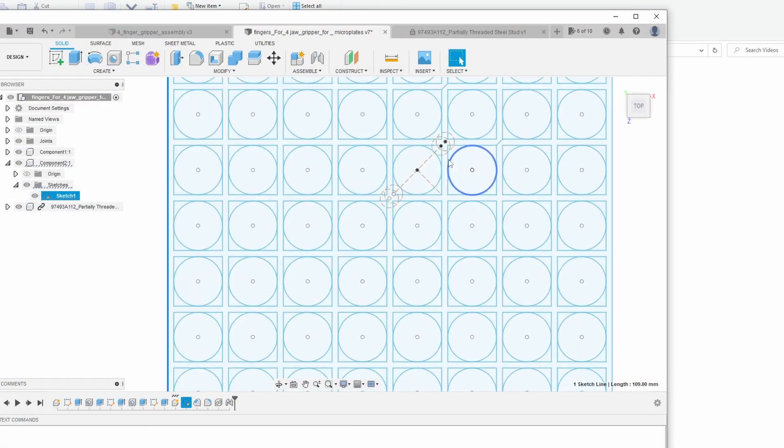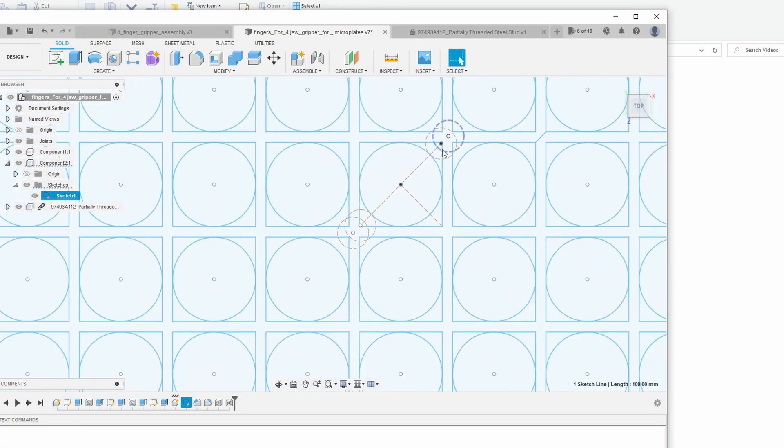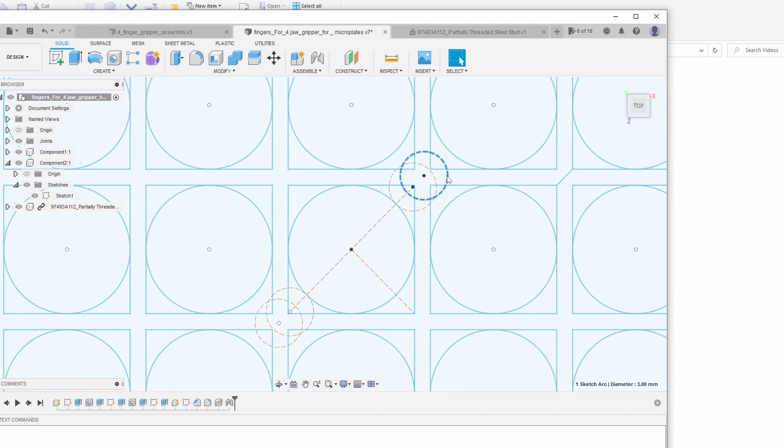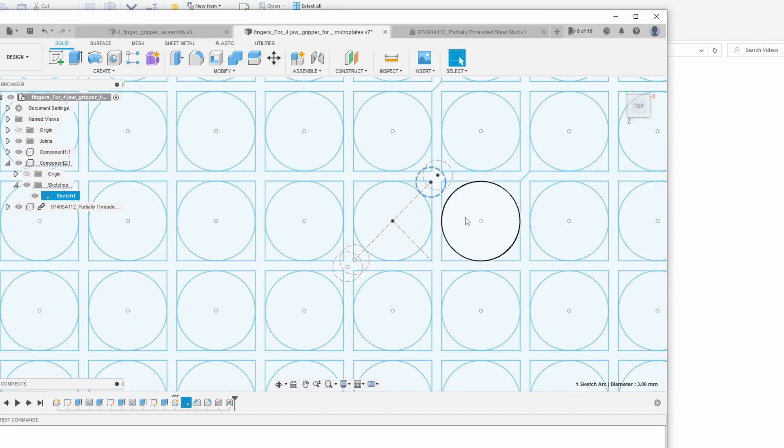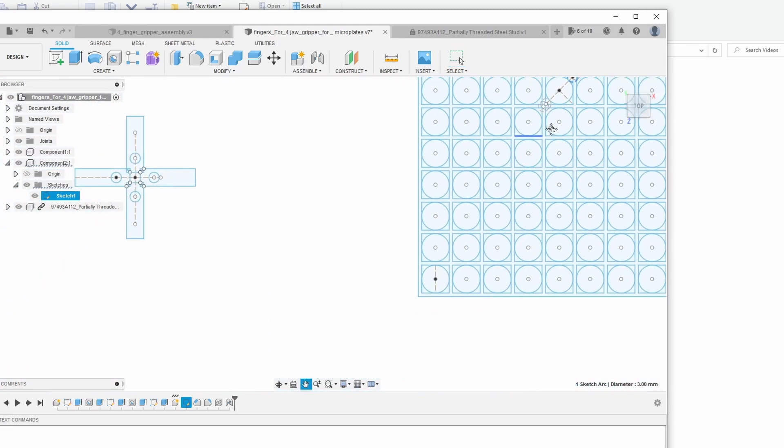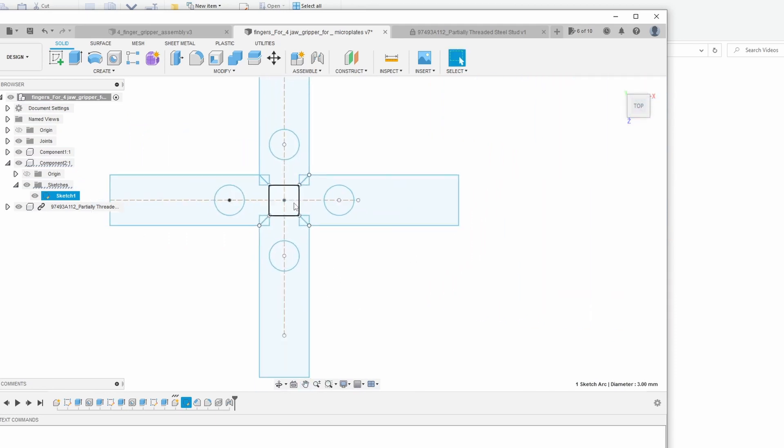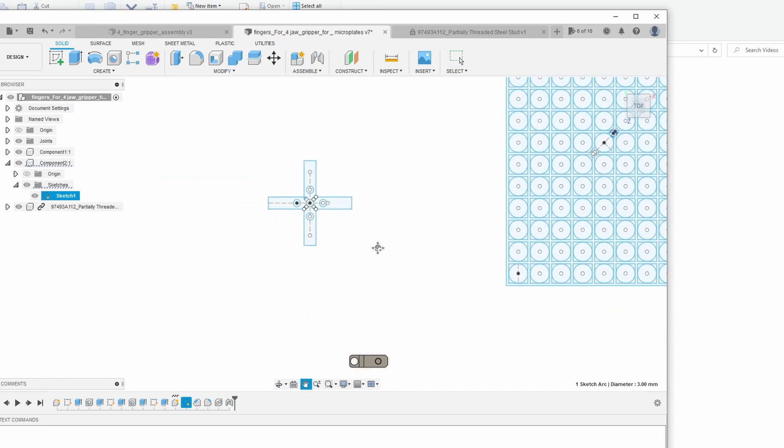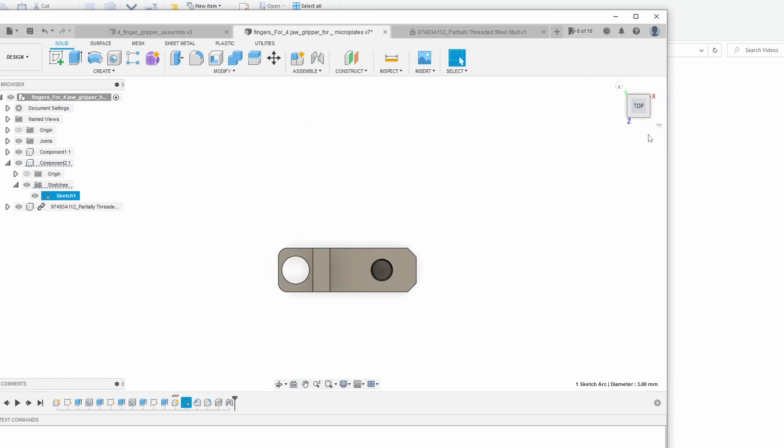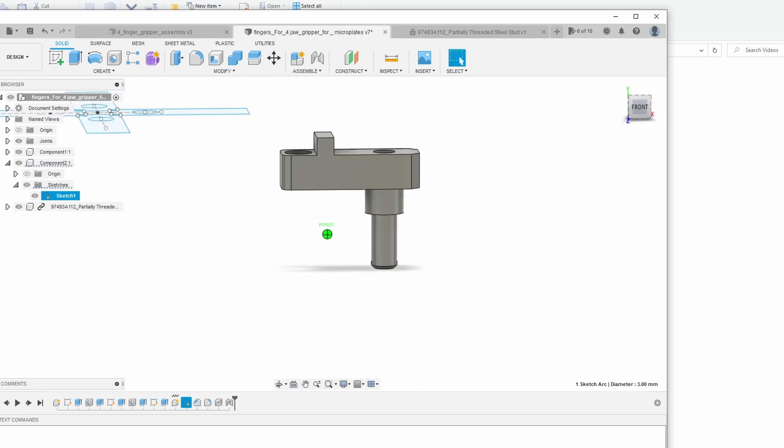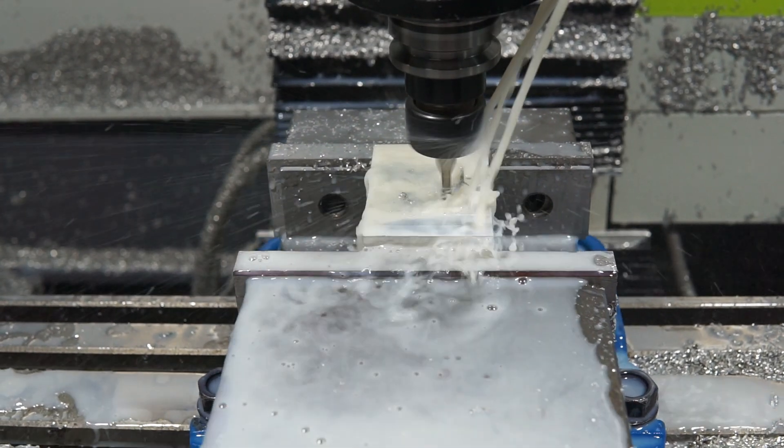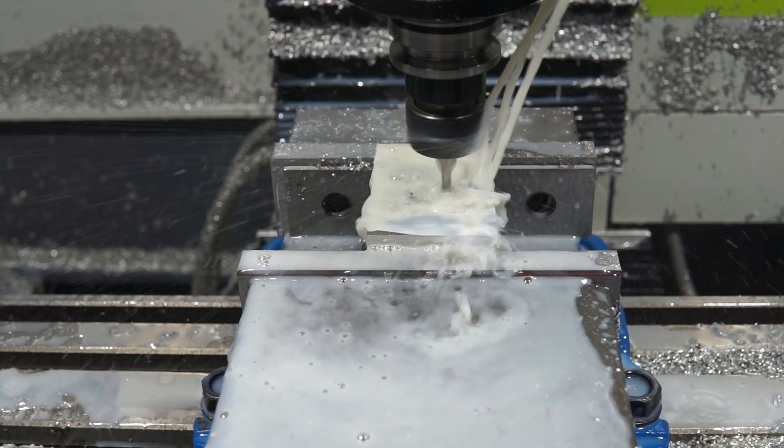We designed the base of the finger so when the gripper is open the tips are in the middle of the space between the microtubes and when the gripper is closed the tips are surrounding the tubes. This means that we need to limit the travel of the gripper jaws from 4 mm to 2 mm. For that we designed the bases such that they collide and stop the jaws at 2 mm travel limit. The bases are machined out of aluminum for sturdiness and durability.